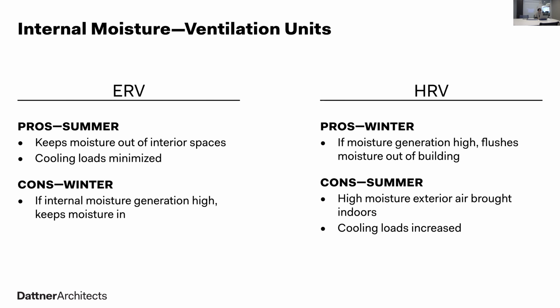Humidity in the winter was also a concern because the ERVs are so efficient at retaining latent heat that they're not exhausting much of the moisture produced in the building. So in winter, we could potentially have a condition where we have relatively high relative humidity indoors and low temperatures outdoors. And what we want to avoid is creating condensation at or within the facade.